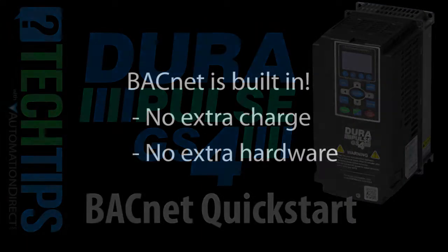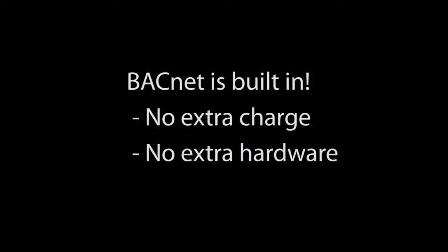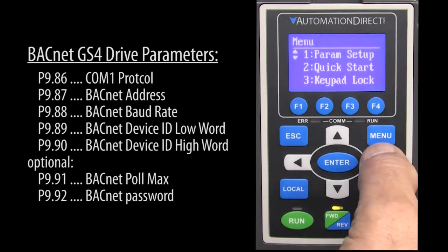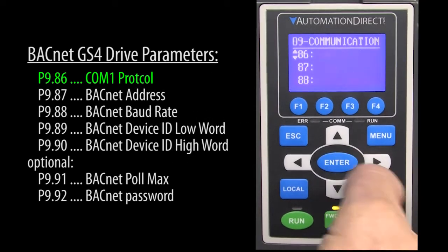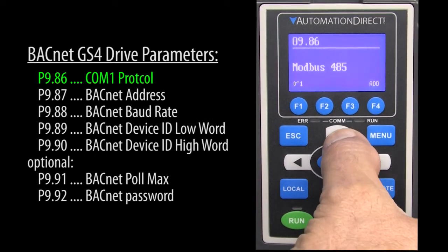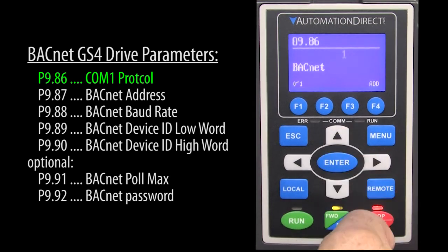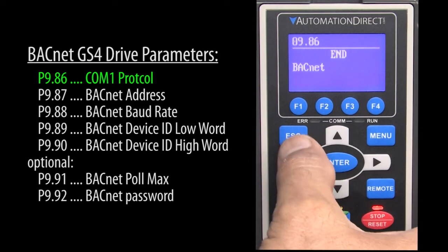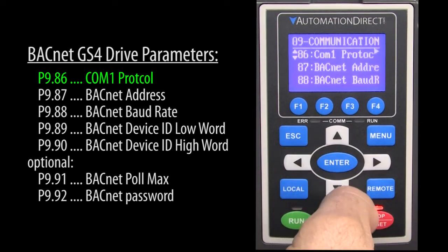GS4 drives have BACnet built in. That's right — there's no extra charge for BACnet and it's so easy. You just go to parameter 9.86 and switch the RS-485 COM port to BACnet mode instead of Modbus mode.